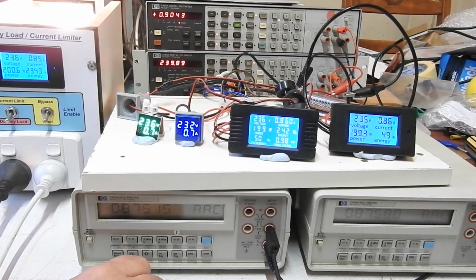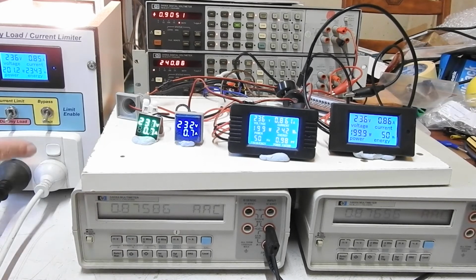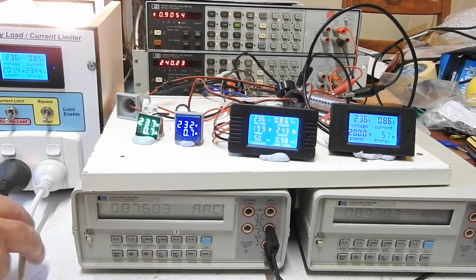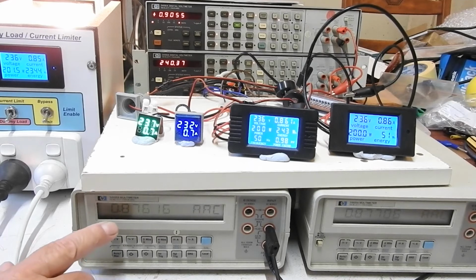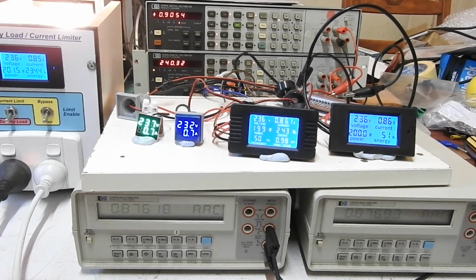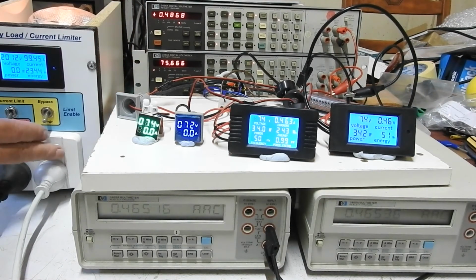Alright, now to measure currents higher than that, I'm going to have to turn on the space heater down below, the oil-cooled heater, and reduce the voltage, because that will draw more than 3 amps. So to get between 0.8 of an amp and 3 amps, I'm going to have to lower the voltage and turn this thing on. So volts down first, and turn this guy on.